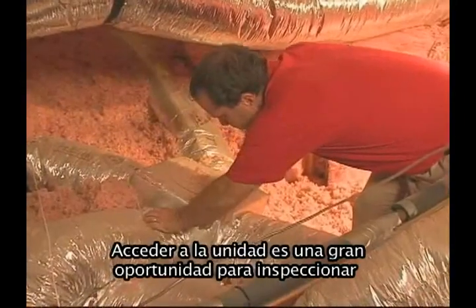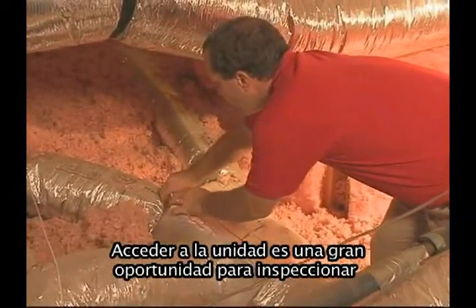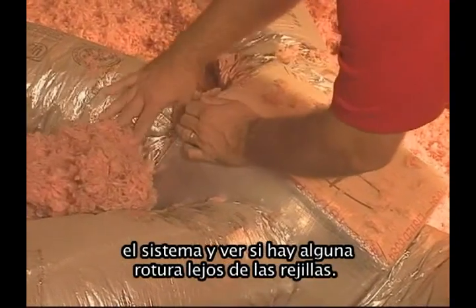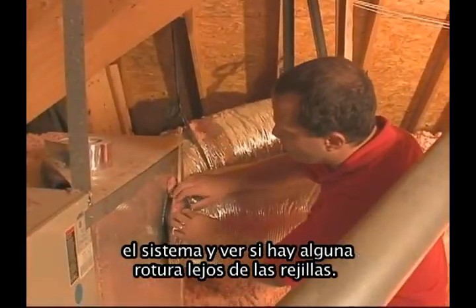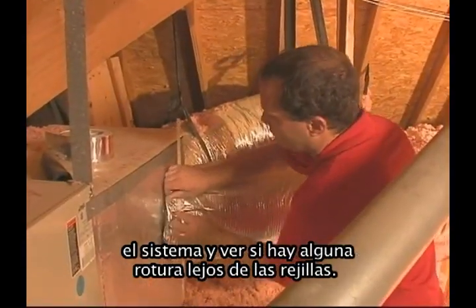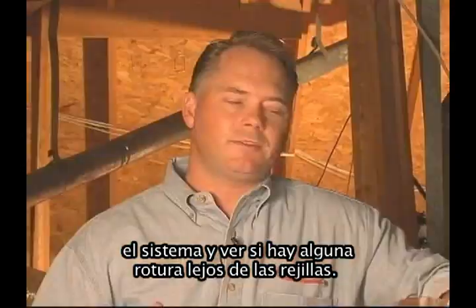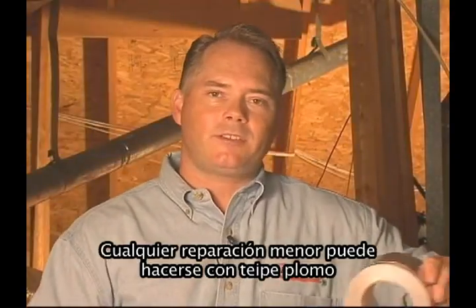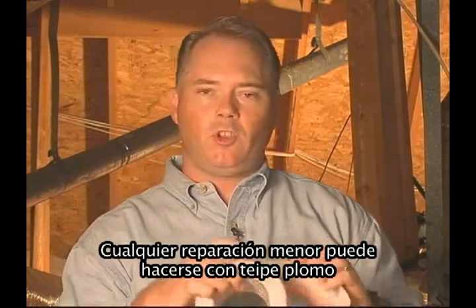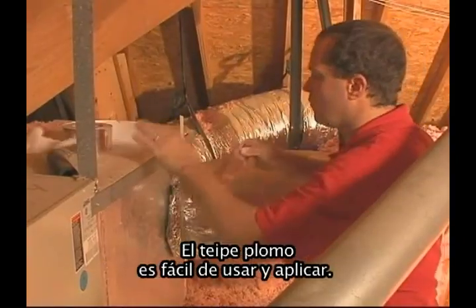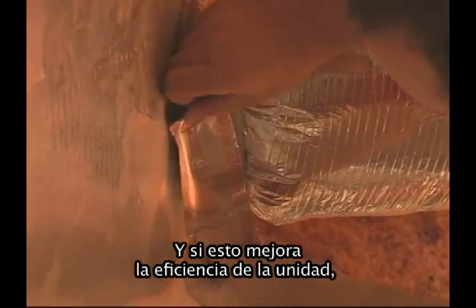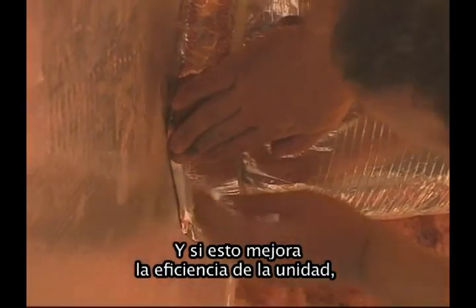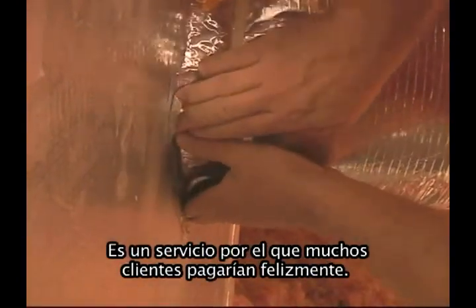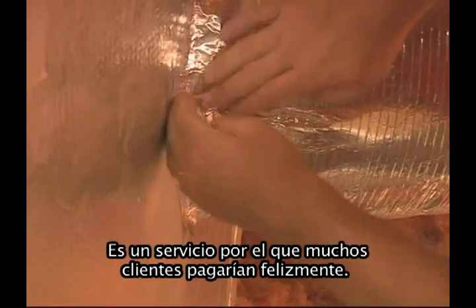While at the air handler, this is a great opportunity for you to inspect the ductwork throughout the system and look for any cracks and/or tears and/or ducts that are pulled away from the registers. Any mild and minor repairs can be accomplished with aluminum foil tape. Aluminum foil tape is easy to use and apply. And if this improves the efficiency of the air handling unit, this would be a service that most homeowners would be happy to pay for.